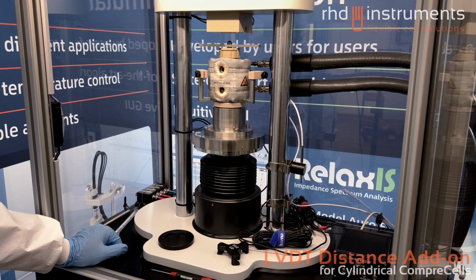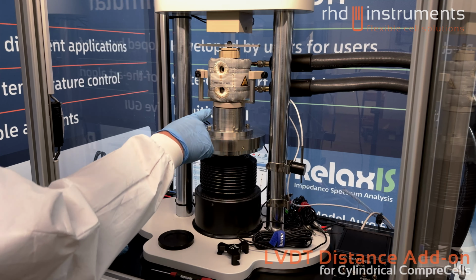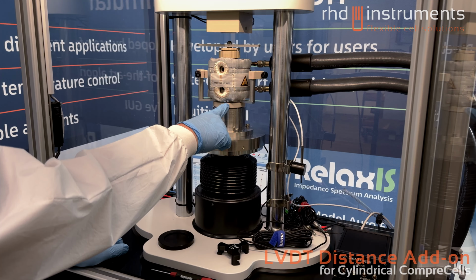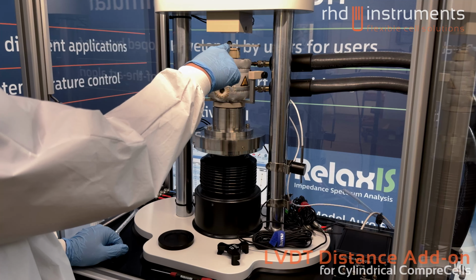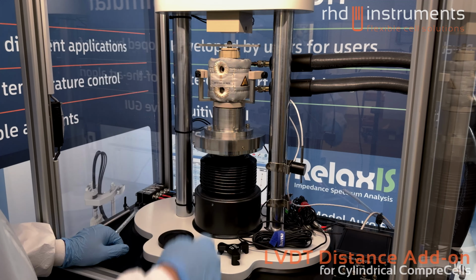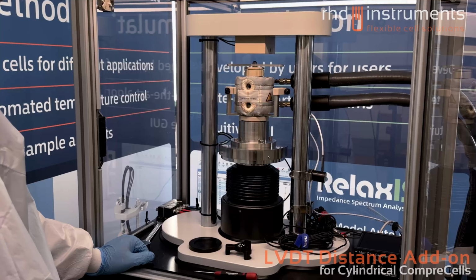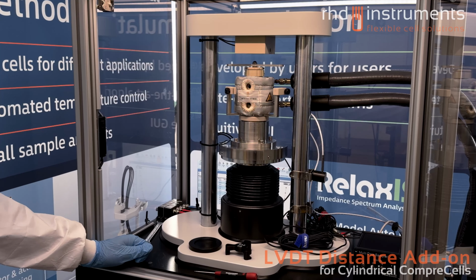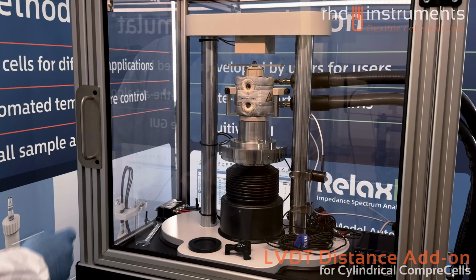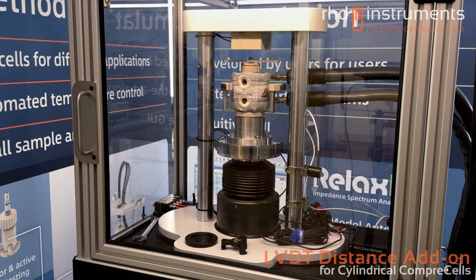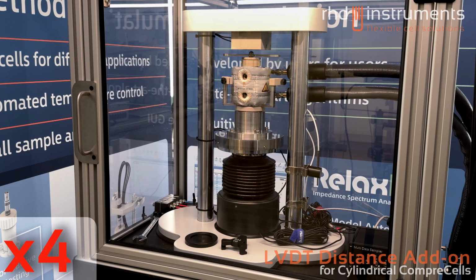Now let's talk a little bit about the assembly. The mounting aids that we used before helped us to adjust appropriate air gaps between the parts of the dilatometer and the cell. So in the bottom you can see that there is a small air gap between the PEEK ring of the CompreDrive platform, and on the top you can see that there is an air gap between the lids of the cell and the cantilever. We also want to make sure that the sensor holder does not touch the tubes of the circulator. Before we can mount the sensors, we need to approach the CompreDrive. So I will go ahead, close the device and start the approach procedure. Please monitor the cell during the approach. Make sure that you do not see any tipping movements, and if the cell starts to slide off the platform or is misaligned, please hit retract immediately or use emergency stop switch.